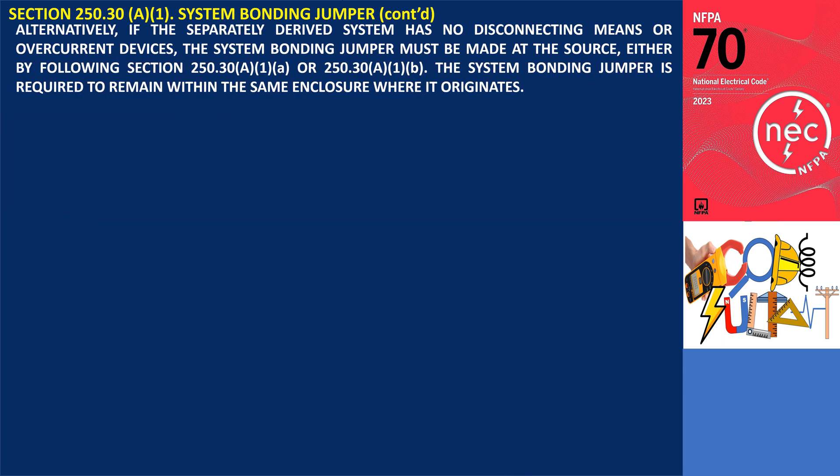Alternatively, if the separately derived system has no disconnecting means or overcurrent devices, the system bonding jumper must be made at the source, by either section 250.30 A.1.A or 250.30 A.1.B.